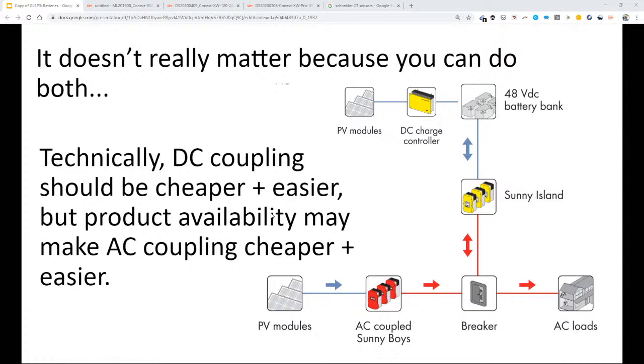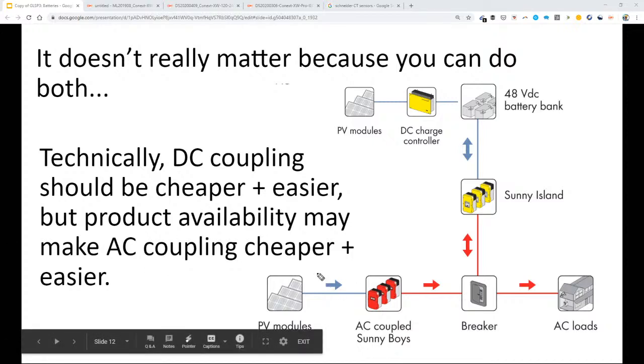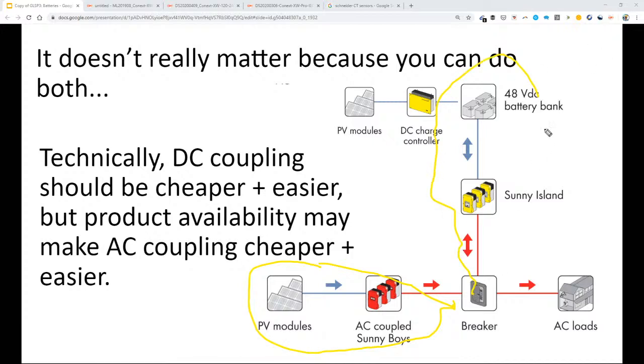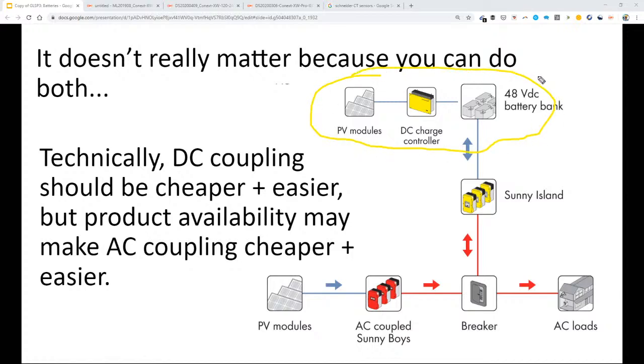Now, if you go on battery discussion forums, they'll talk about charge controllers versus battery inverters—one's DC to DC, the other's DC to AC. That leads to a discussion: is it better to have the solar array on its own inverter AC coupled to the battery inverter, or to have the solar array plugged directly into the batteries with the whole system on one battery inverter?